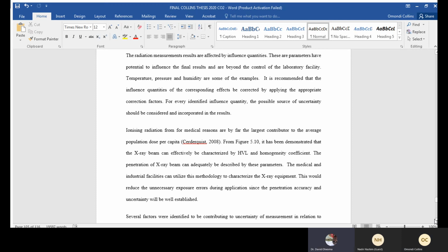And also in your conclusions, because people will be wondering, especially people who are not conversant with the role of Kenya Bureau of Standards and the Secondary Standard Dosimetry Laboratory in particular, they should know that the reason we calibrate the survey meters is that these calibrations are to be conducted in an isolated area and a facility where the background radiation is low. You see the way you have built your bunkers. You can't compare them with where these equipments are used.